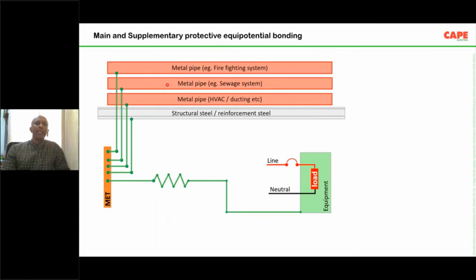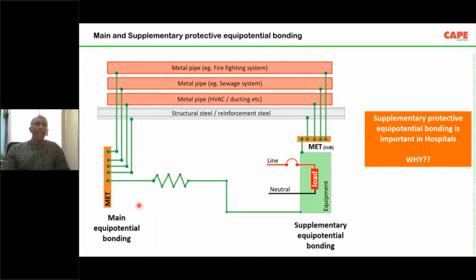You have different metallic installations such as metal firefighting pipe, sewage pipe, HVAC duct, structural steel, and so on. We are supposed to make an equipotential bonding at the main distribution board, and similarly one more protective equipotential bonding at the sub switch board. Here the first one is called main equipotential bonding, the second one is called supplementary equipotential bonding. Now when we come to a hospital environment, supplementary protective equipotential bonding is highly important. Imagine you have an operation theater on the 5th floor. At the operation theater, between the electrical apparatus, between the medical equipment, between the metal pipes, metal gas pipe, metal oxygen pipe, or maybe the wash basin or other structures, everything we are supposed to interconnect.